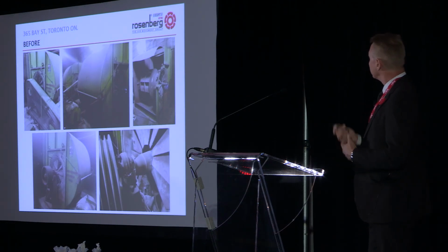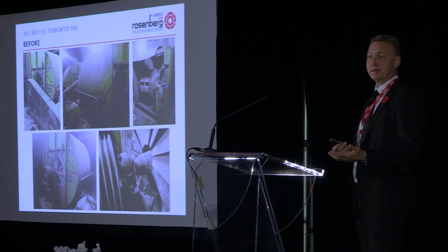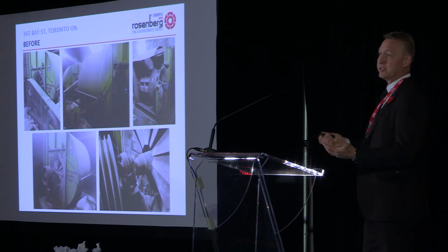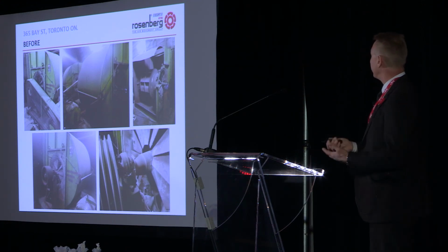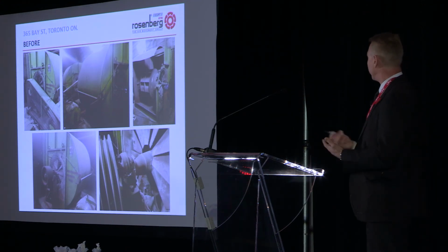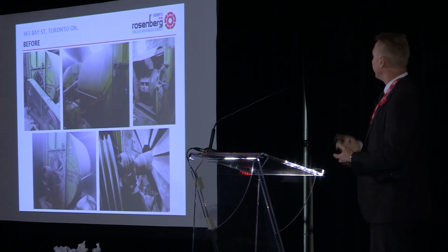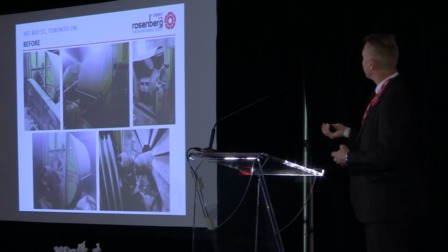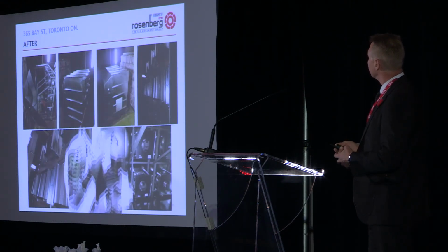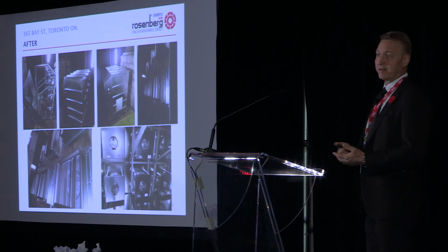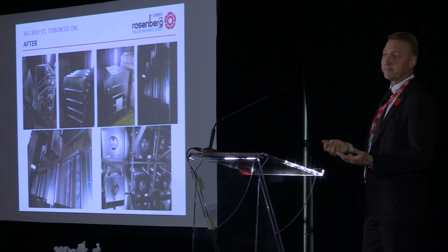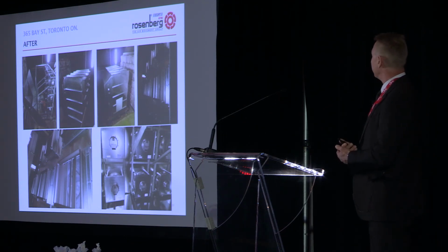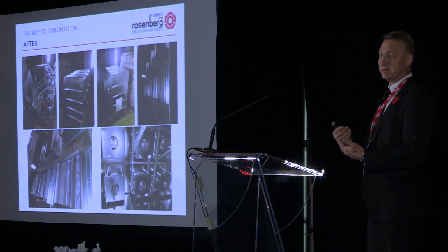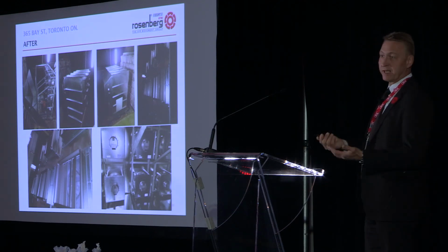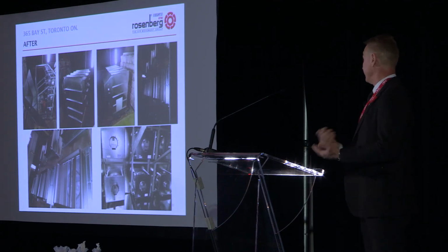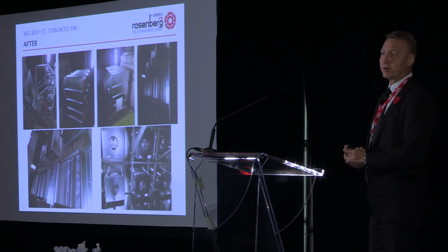The second project was done actually with the Ambient Mechanical. And again, the motivation was the same. The customer wanted to save on capital expenses by replacing the fan. On the fan replacement, the fan was kind of dead, and there wasn't a problem. And here is what was built instead. It was a 9-fan fan grid, constructed in 3x3 configuration. The customer requested the energy savings analysis from the professional firm, and the analysis showed that the savings were close to $25,000 a year.